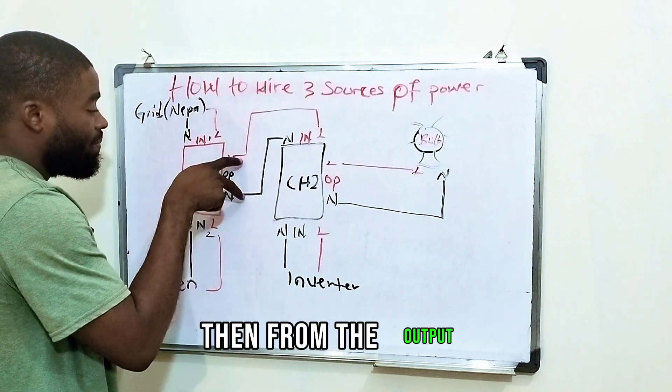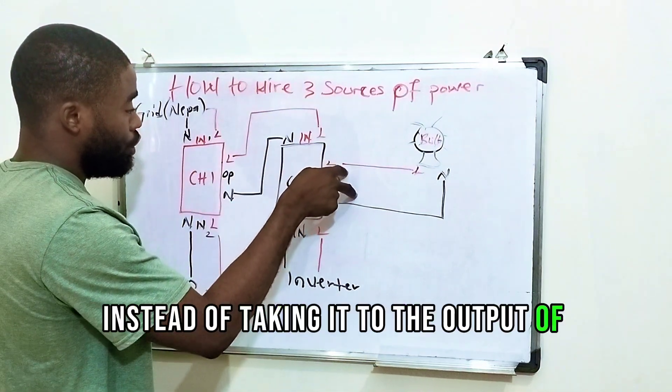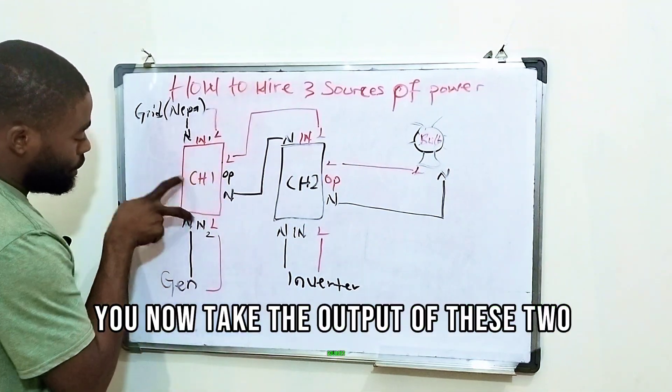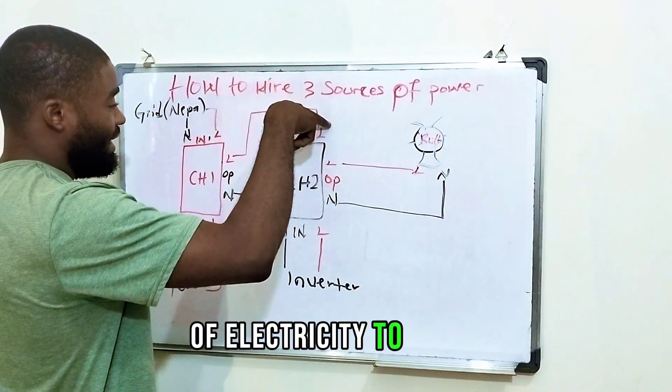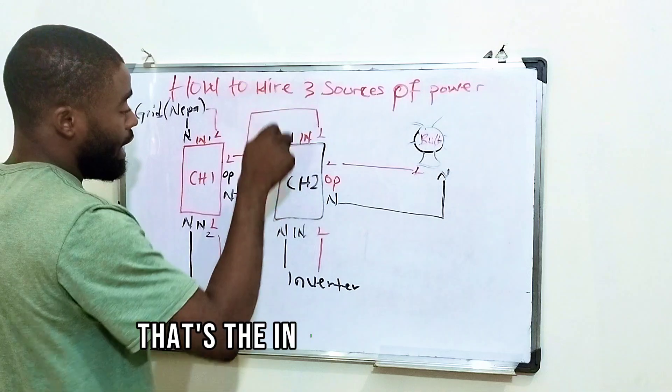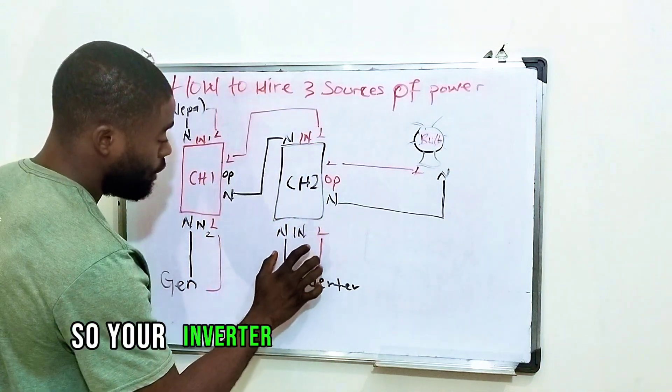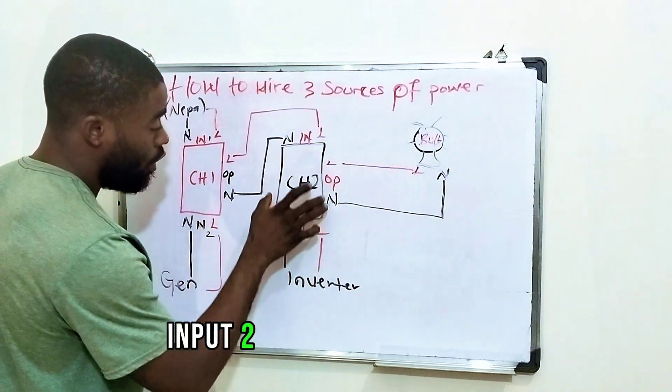Then from the output, instead of taking it to the output of changeover two, you now take the output of these two sources of electricity to the input one of changeover two. So your inverter will be connected to the input two of changeover two.